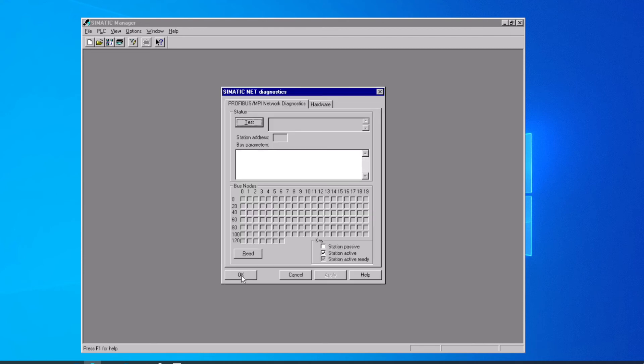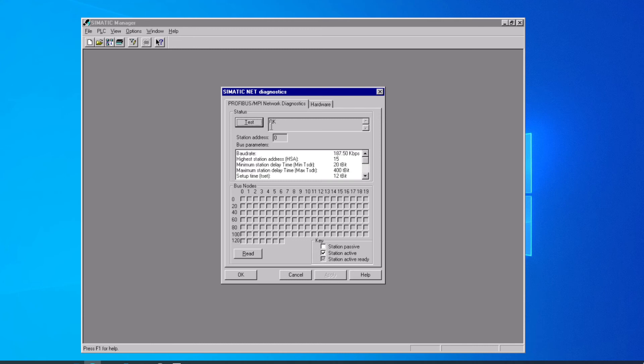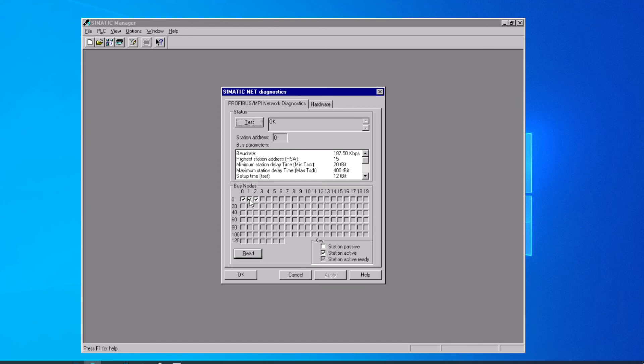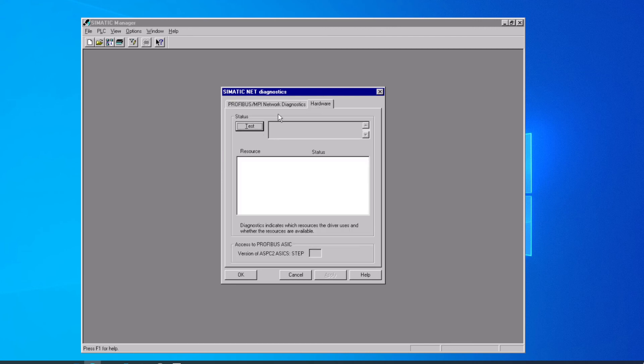The built-in port and some of the other higher-end interface adapters have diagnostic tests where you can go out and check the baud rate on the network, look and see what your MPI properties are. We can also go out and read all the nodes that it can find on the network. We told it to look from 0 to 15, and it found 0, 1, and 2 available on the network.